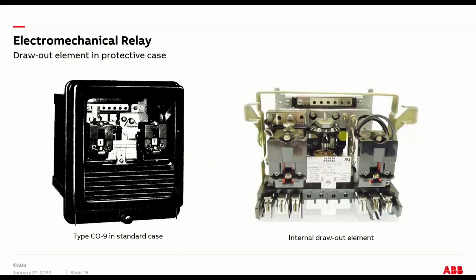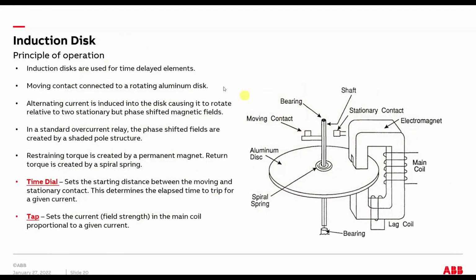Here's a nice slide showing the internal component. This is the actual relay itself that's been drawn out of the box. This is kind of a bad picture, but you can see this is an overcurrent relay, and I'll get into some more of the details later. Basically, the overcurrent relay uses an induction disk to time itself for the time overcurrent portion of the protection. There are 2 basic settings for an induction disk time overcurrent: the time dial, which sets the delay, and the tap, which sets the pickup. That's it. Now you get into your multifunction relays and things get really complicated, but if you go back to the basics, it's 2 settings: time dial and tap.